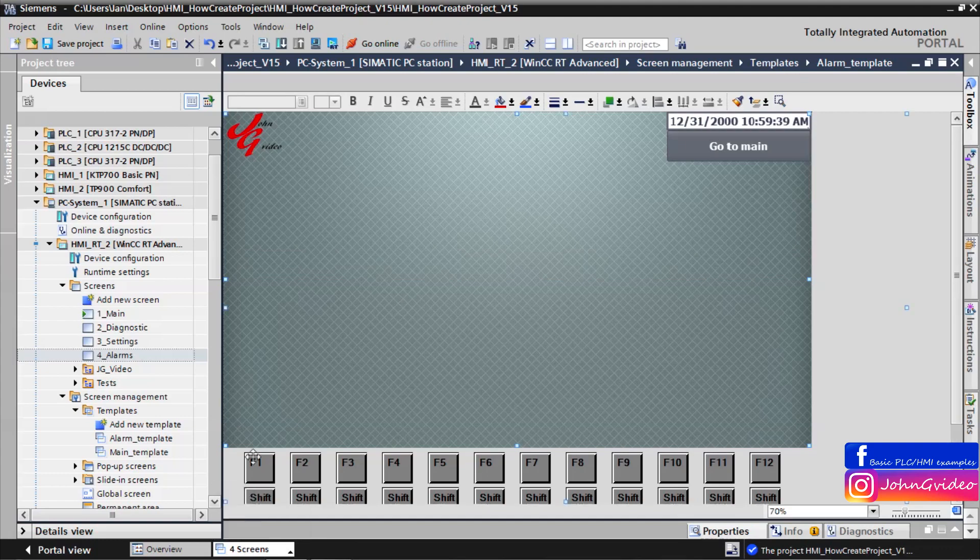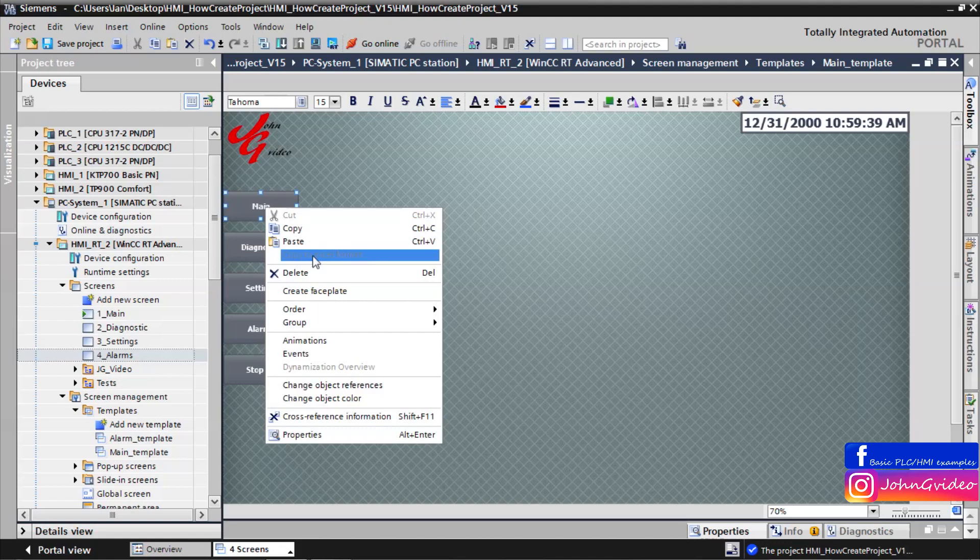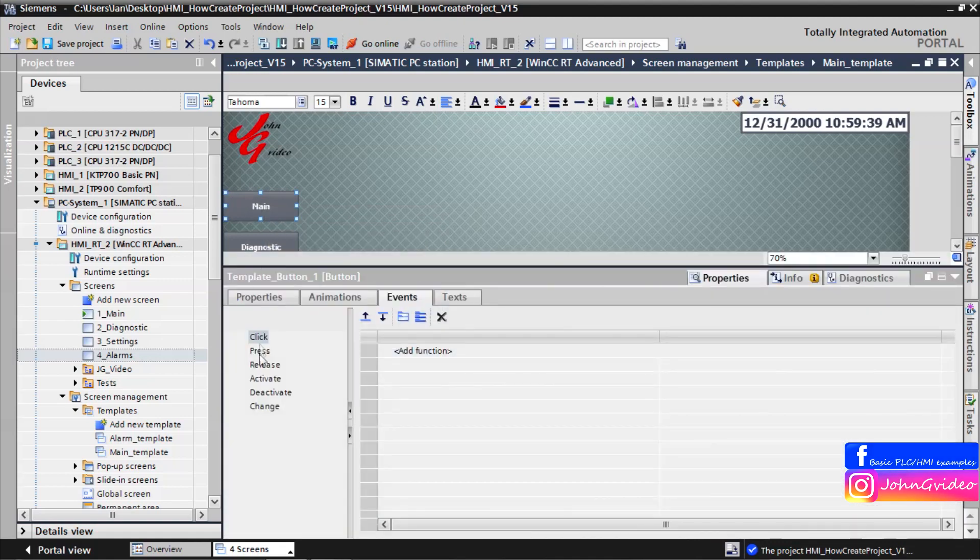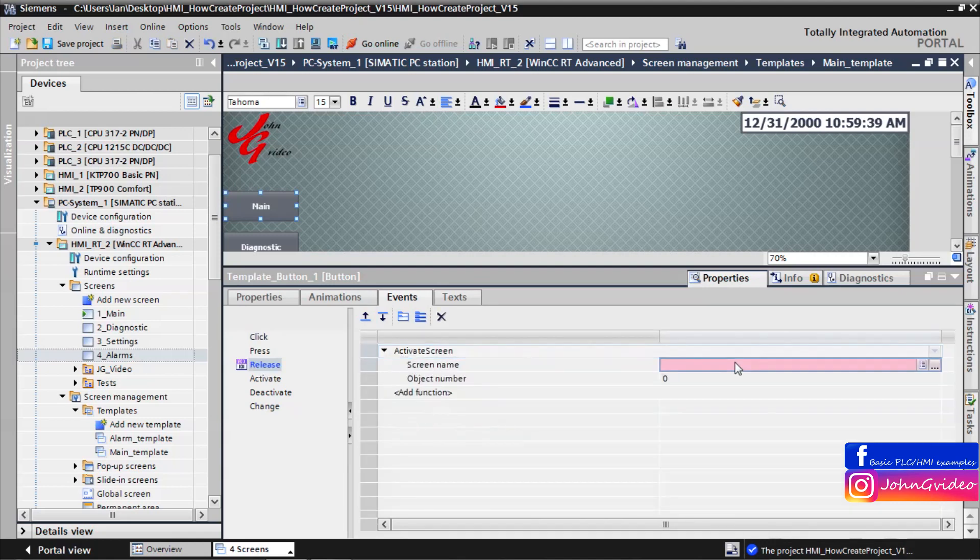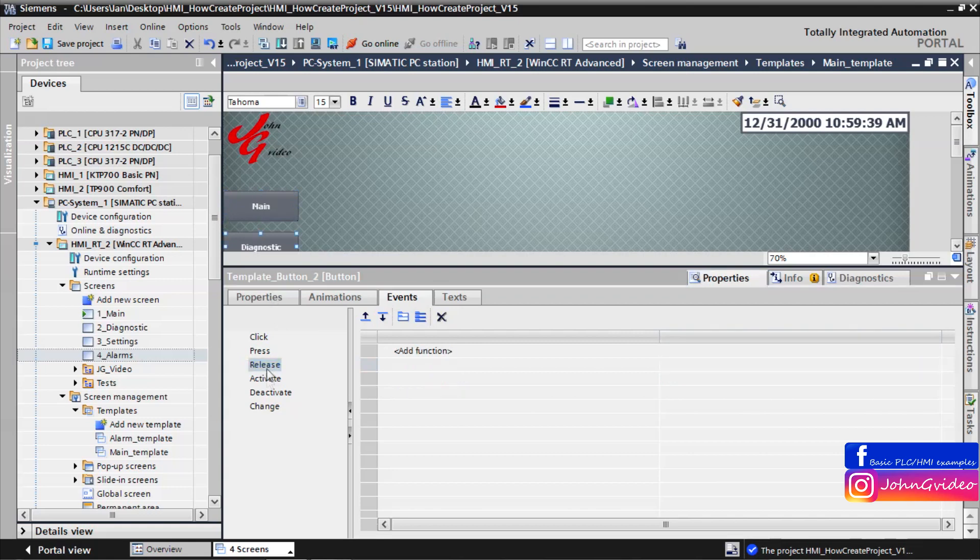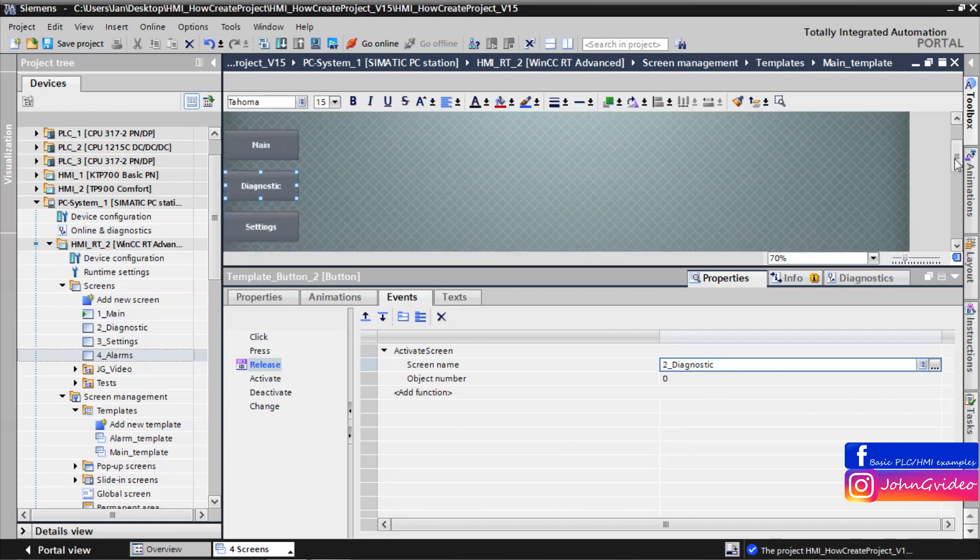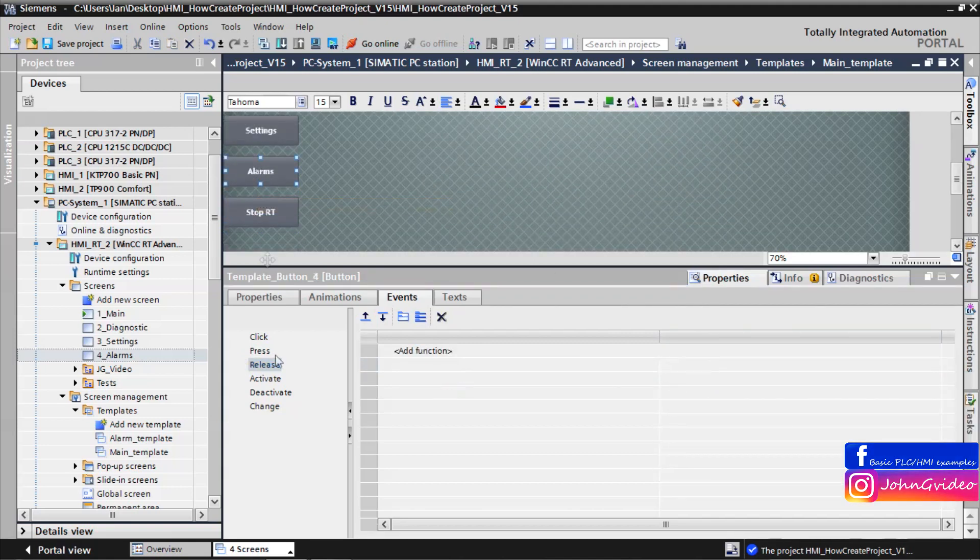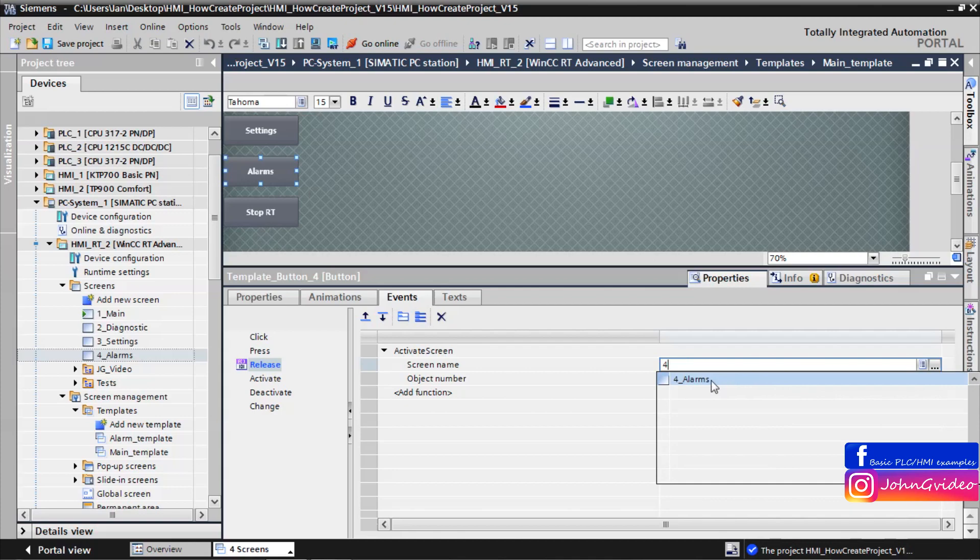Also we make events for menu buttons in main template. After releasing button Main, we activate screen number one Main. We can copy this event. Paste to the diagnostic button. But we change screen name to number two, Diagnostic. Same for settings, screen name number three Settings. And for alarm button, activate screen number four Alarms.